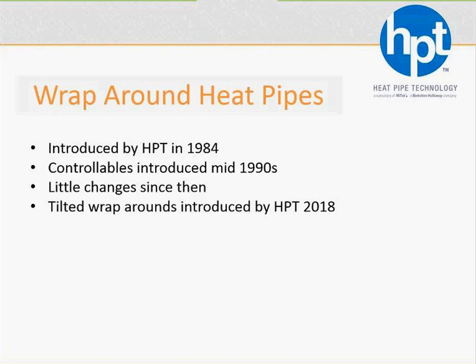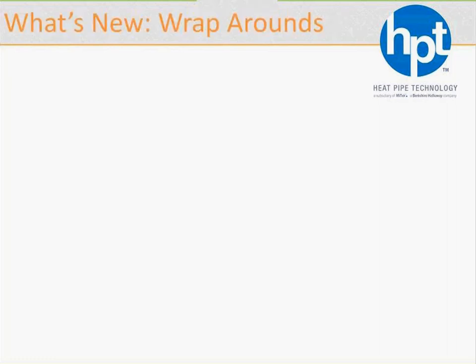Starting with wraparound heat pipes. They were introduced by Heat Pipe Technology back in 1984, where the first wraparound patent was granted. At the request of the engineering community, early 1990s, we started adding valves to individual circuits, and that led to the birth of controllable heat pipes that controlled basically how the heat pipes go from 0 to 100%. At heat wave conditions, when you don't want so much reheat, you start turning off those circuits, which is typically done in stages. Little changes took place since then until earlier last month when HPT introduced what we call second generation wraparound heat pipes. We'll share with you those in the next slide.